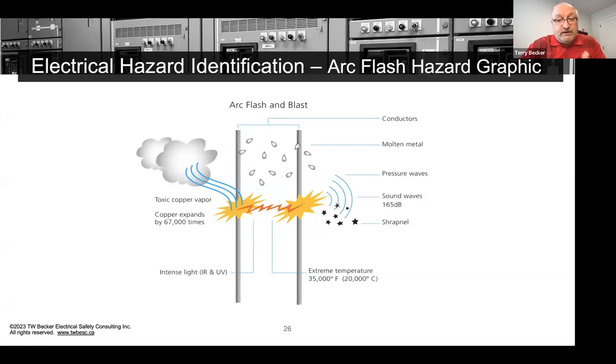So that's incident energy. We get molten metal. Obviously, we get that instantaneous noise, the bang we hear, right? And then we get the toxic vapor. And again, there's multiple effects. Most PPE protects for all of this, except for the blast pressure specifically. And you don't need any pressure-related PPE for workers exposed to arc flash.